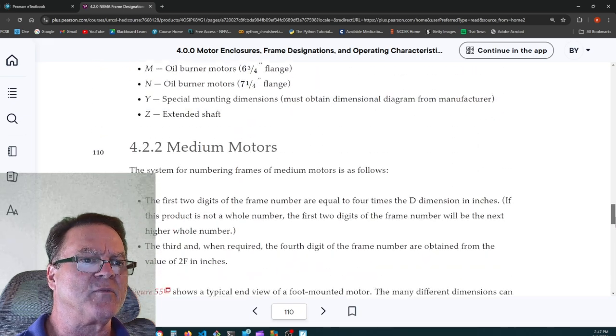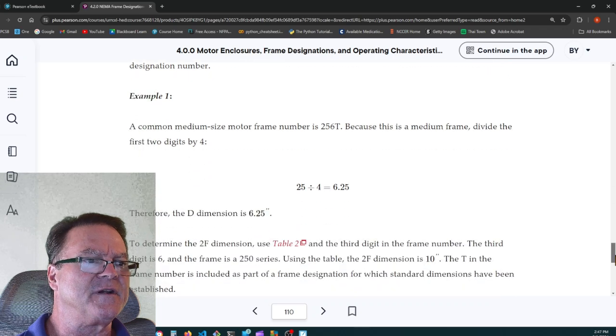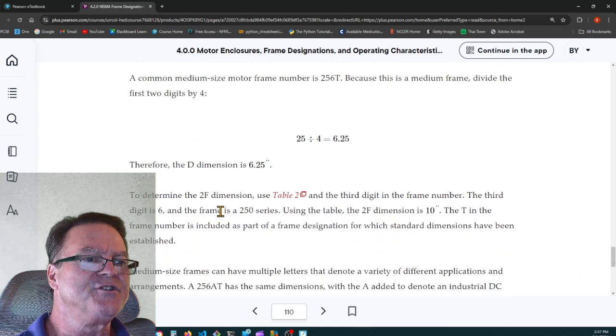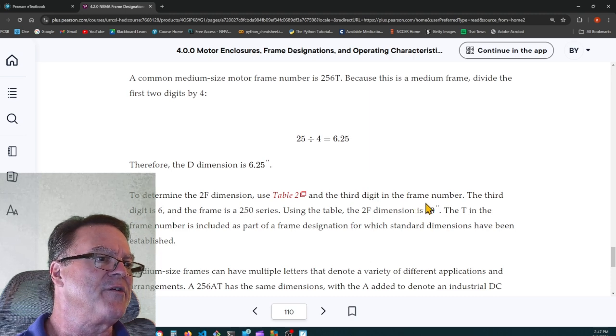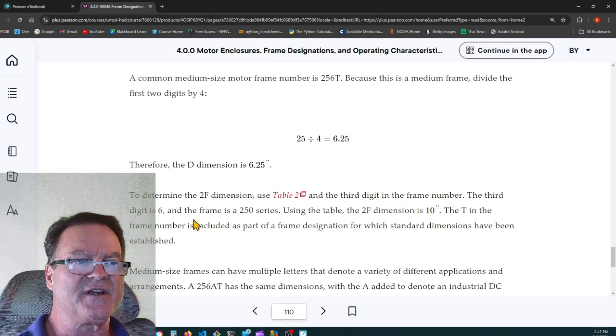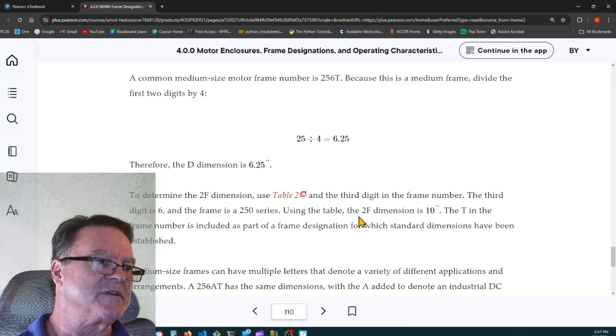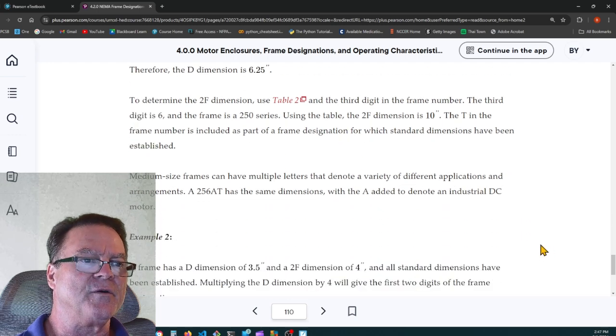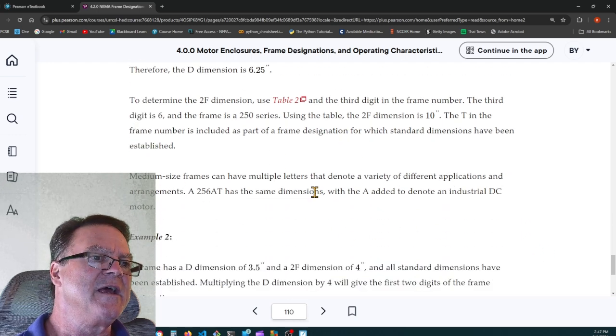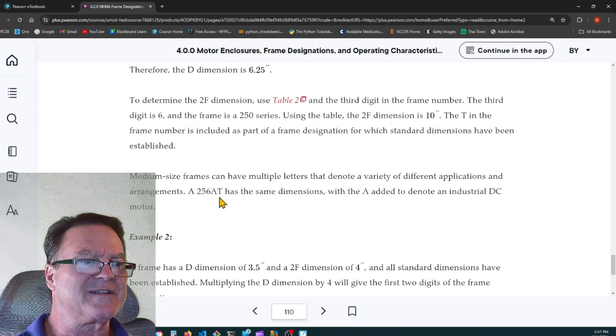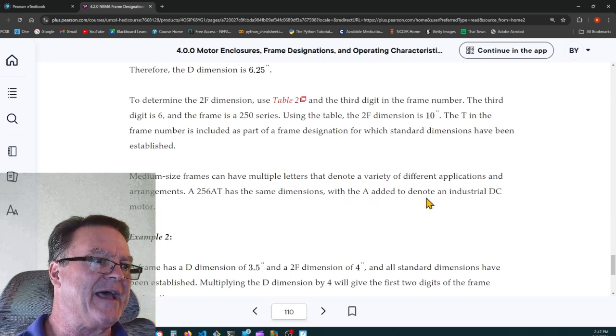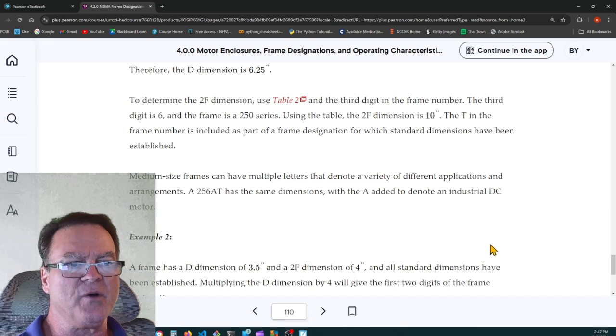Okay. Let's go back to the example. Where did I go here? I've lost it. Here we go. All right. To determine the 2F dimension, use table 2, and the third digit of the frame number. Third digit is a 6, and the frame is a 250 series. Using the table, the 2F dimension is 10 inches. The T in the frame number is included as part of a frame designation for which standard dimensions have been established. So, medium-sized frames can have multiple letters that denote a variety of different applications and arrangements. A 256 AT has the same dimensions with the A added to denote an industrial DC motor.